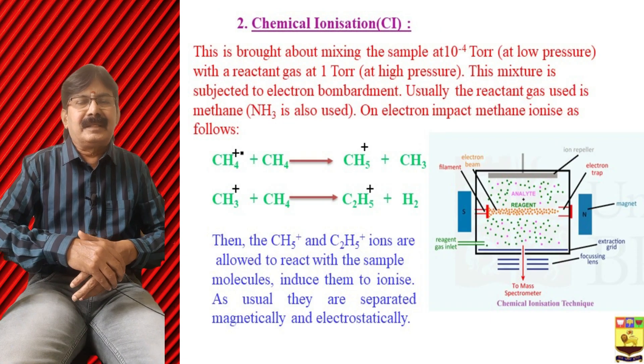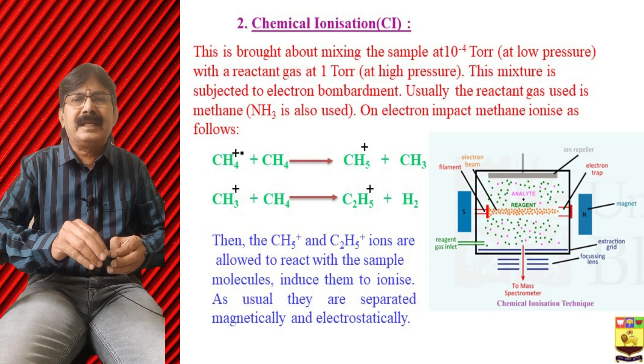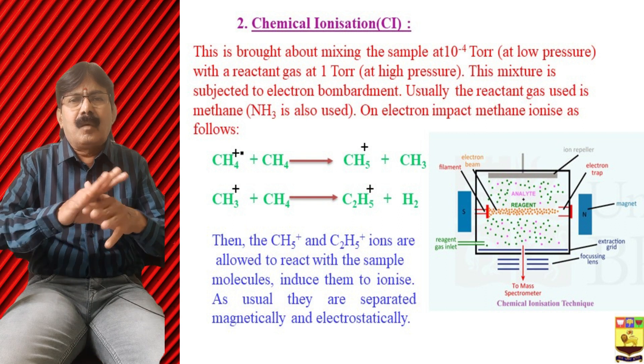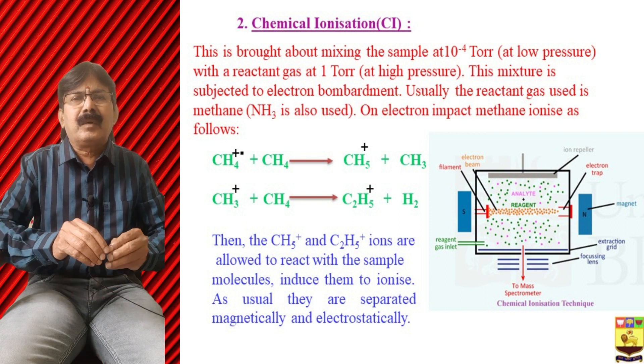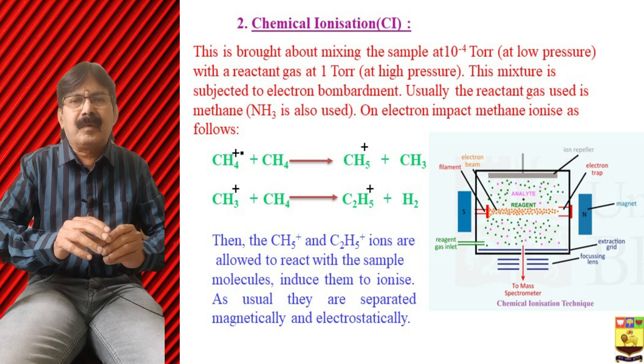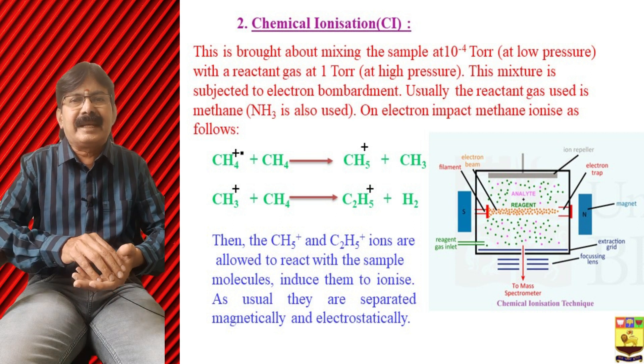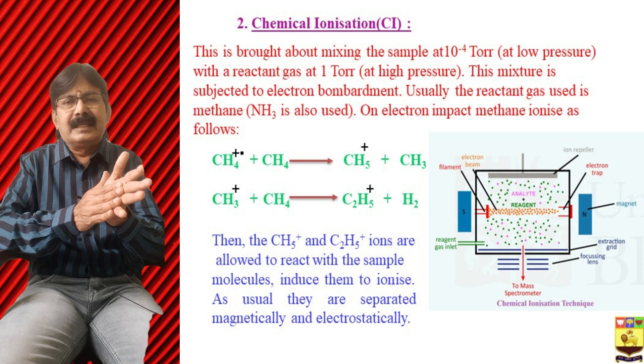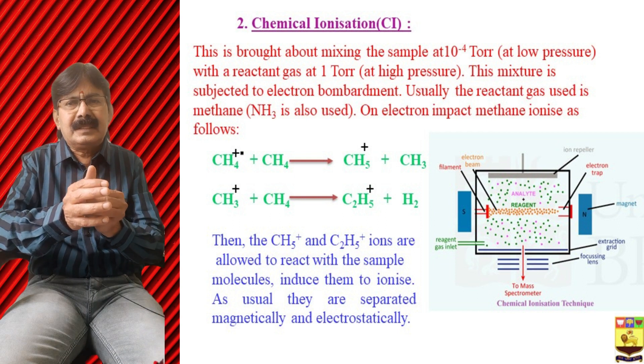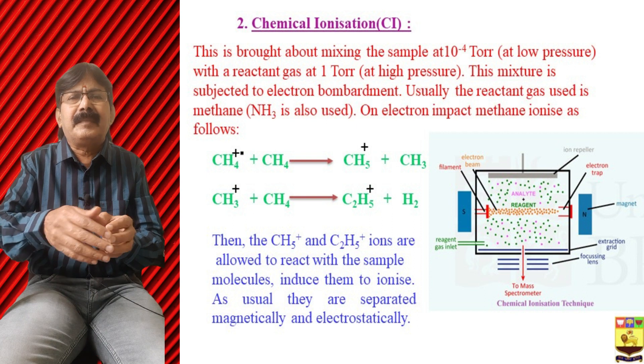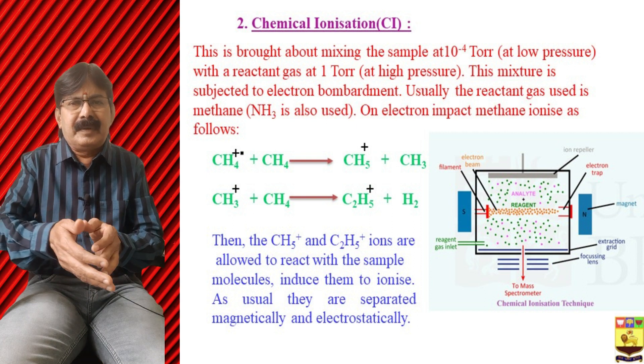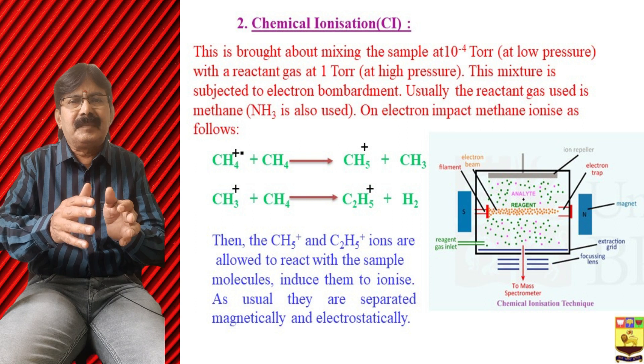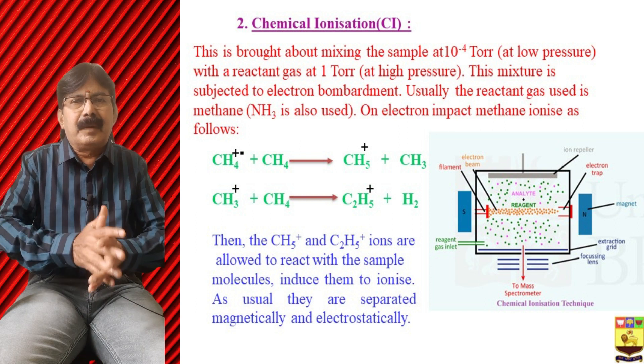The second technique is chemical ionization, which is done by chemical compounds. The sample at a low pressure of 10 to the power of minus 4 Torr is mixed with a reactant gas at 1 Torr — generally methane or ammonia — and this mixture is subjected to electron bombardment.